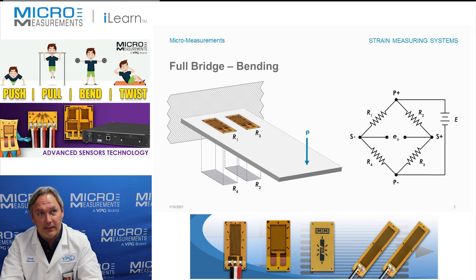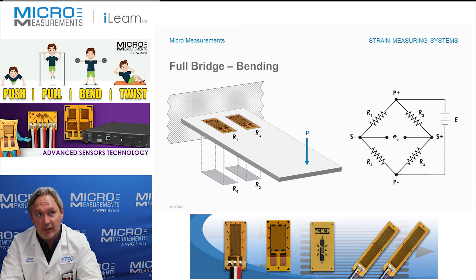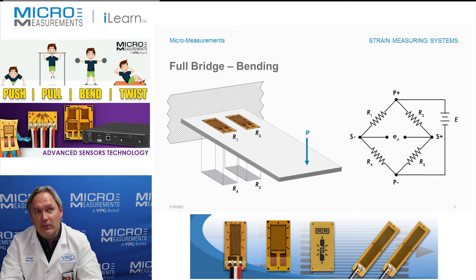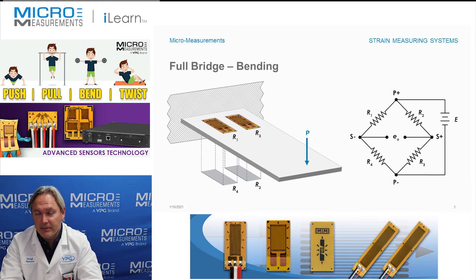We take that and connect it into our Wheatstone bridge. You'll notice P-plus and P-minus for the power coming in, and S-minus and S-plus for the signal coming out. Capital E represents the excitation supply voltage to the circuit, and small e-sub-O represents the signal coming out. We wire it such that R1 and R3 are in opposite arms, and R2 and R4 are also opposite each other.